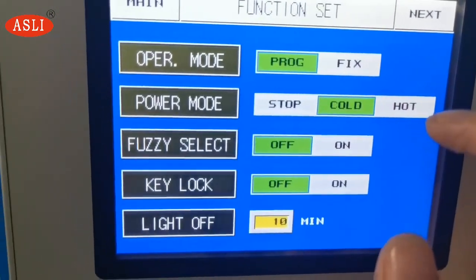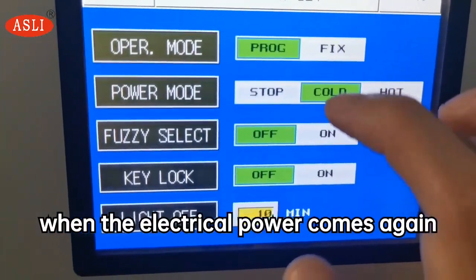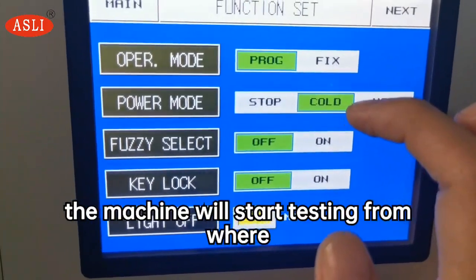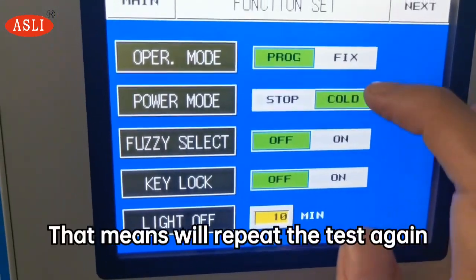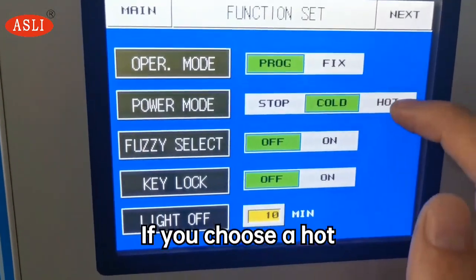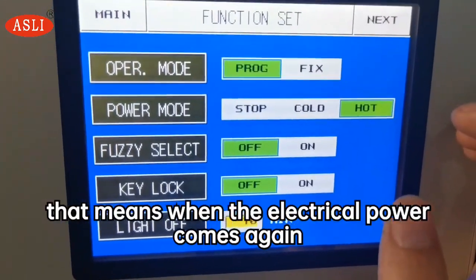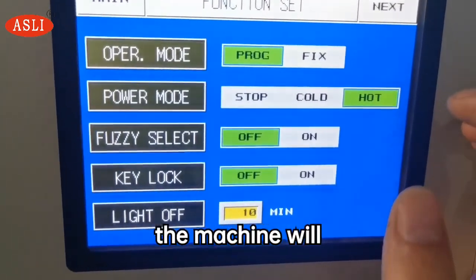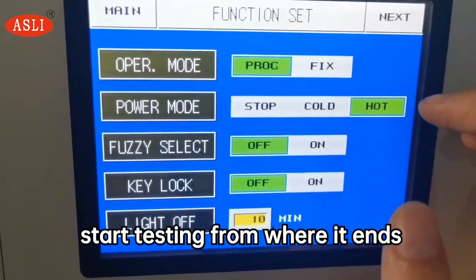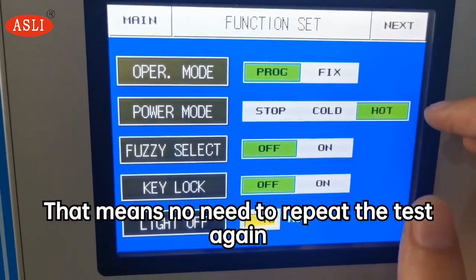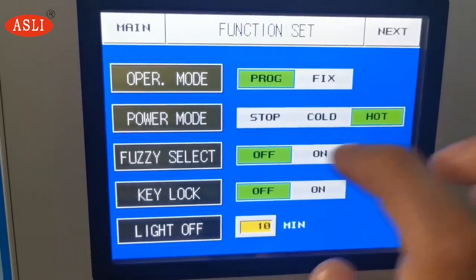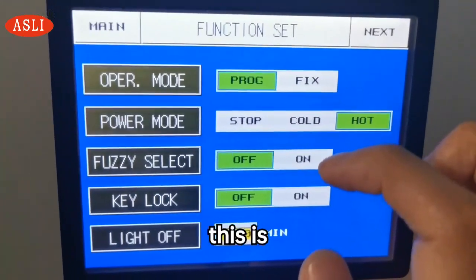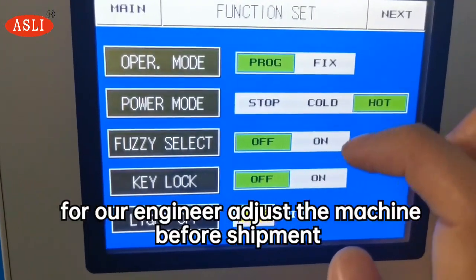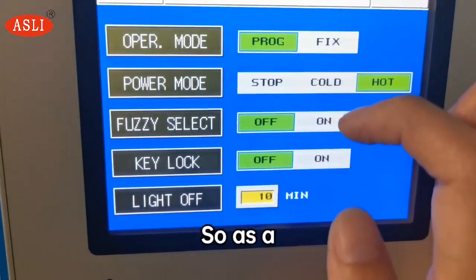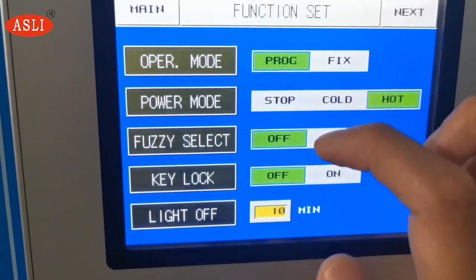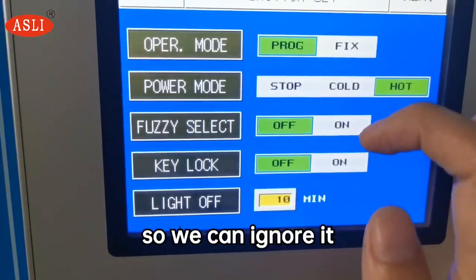If you choose cold, that means when the electric power comes again, the machine will start the testing from the beginning. That means we'll repeat the test again. If you choose hot, that means when the electric power comes again, the machine will start the testing from where it ended. That means no need to repeat the test again. Fuzzy select. This is for our engineer to adjust the machine before shipment. So as a user, we don't need this function, so we can ignore it.